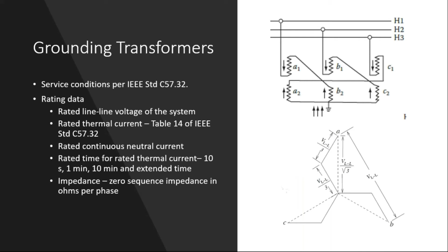Grounding transformers. The grounding transformers are normally connected in a system where you want to create a ground point for grounding purposes, mainly when your system is delta where there is no ground option. You can have a delta Y transformer as a grounding transformer, or delta zigzag, or just a simple zigzag transformer connected to your system for this purpose.